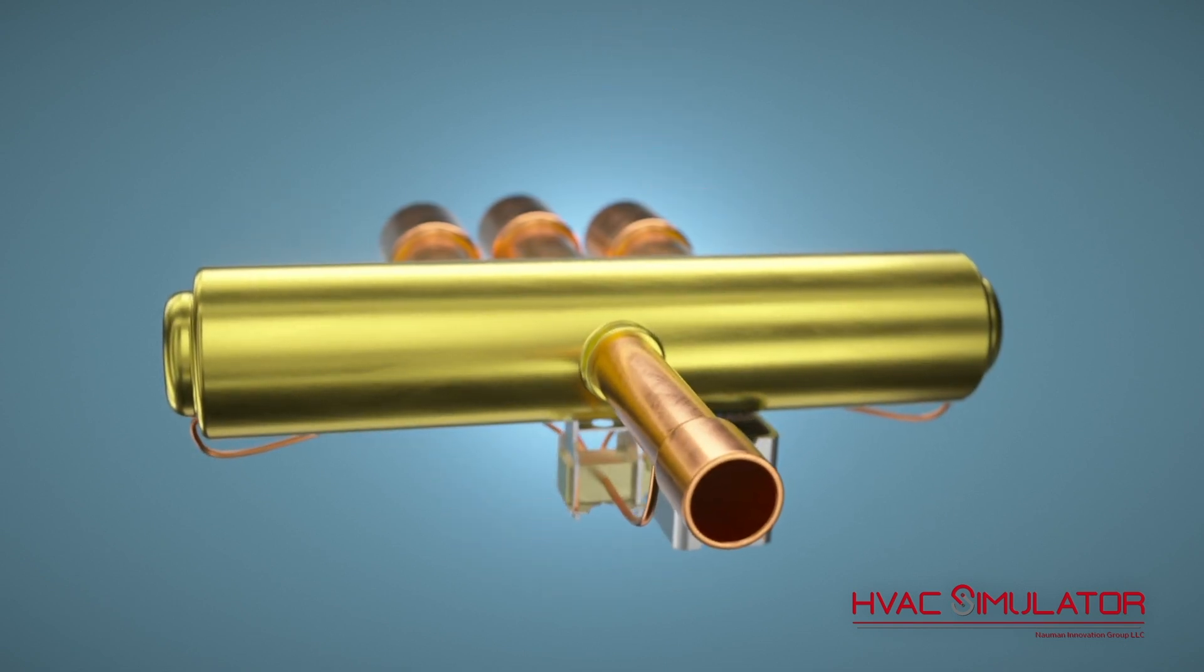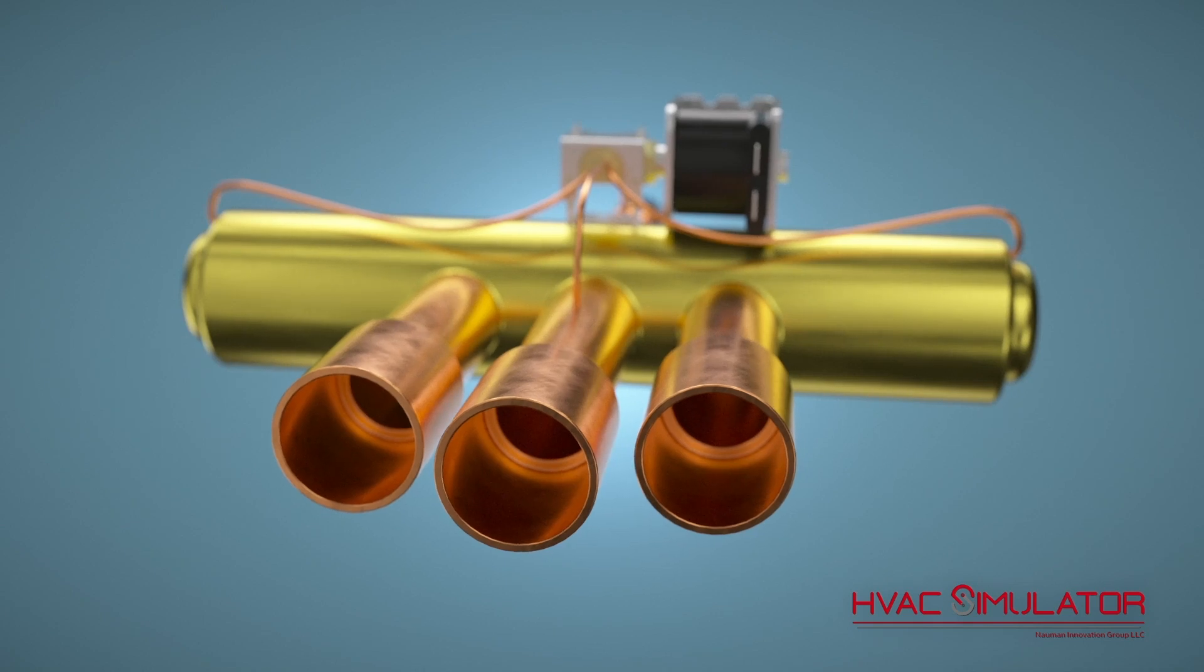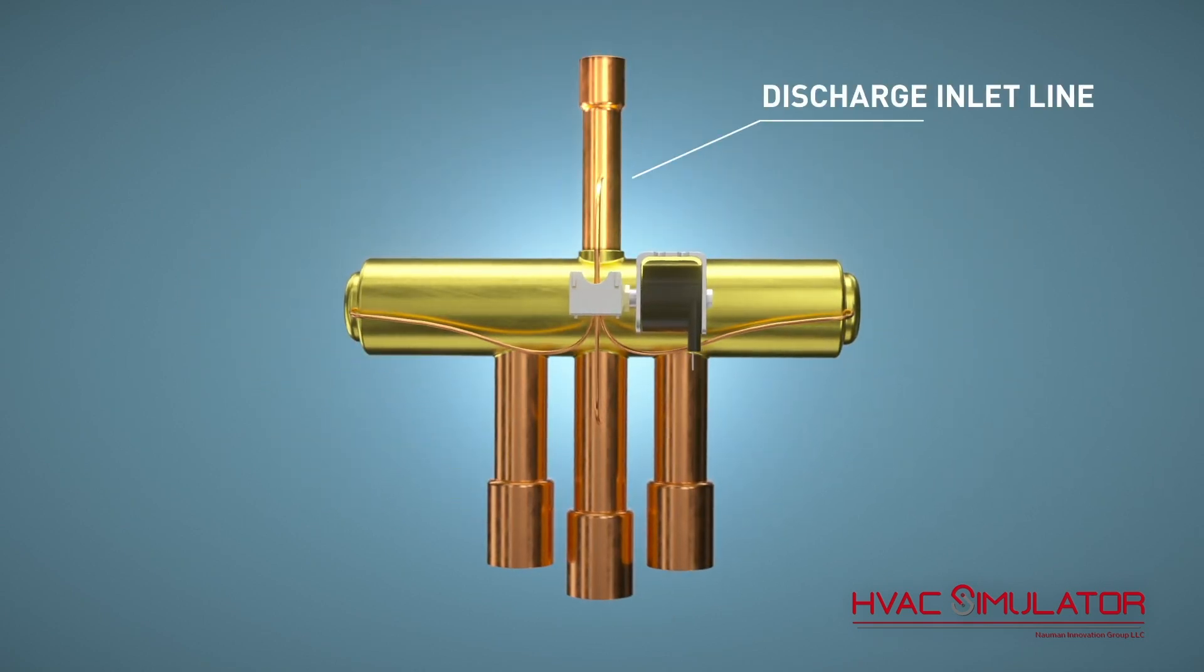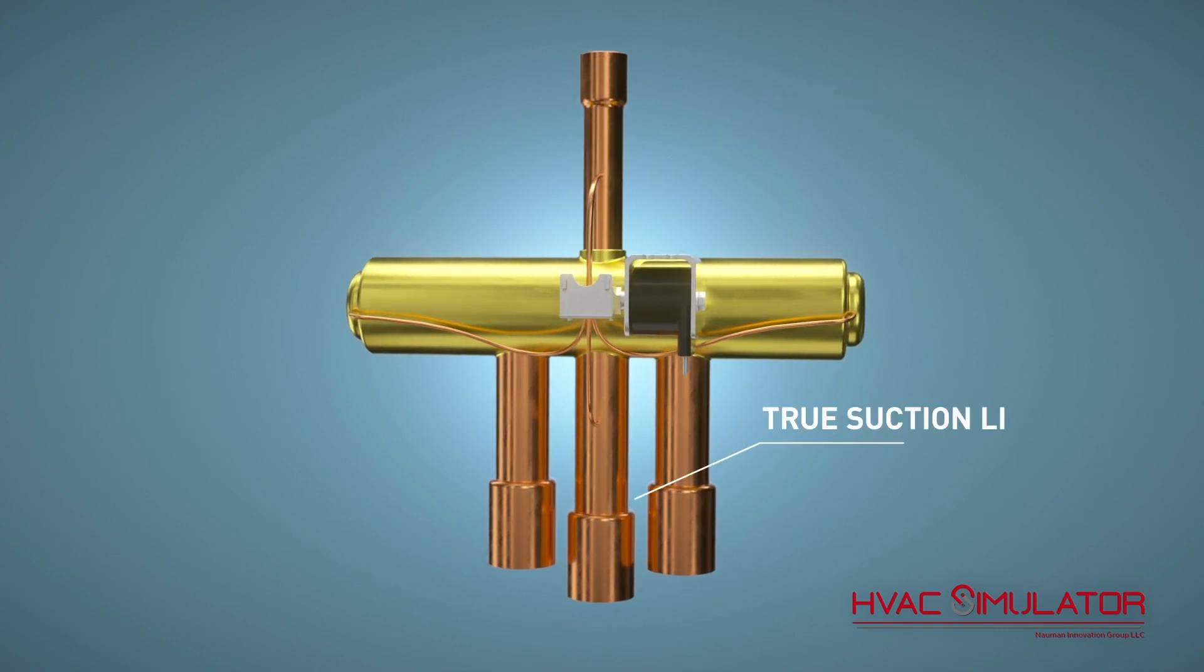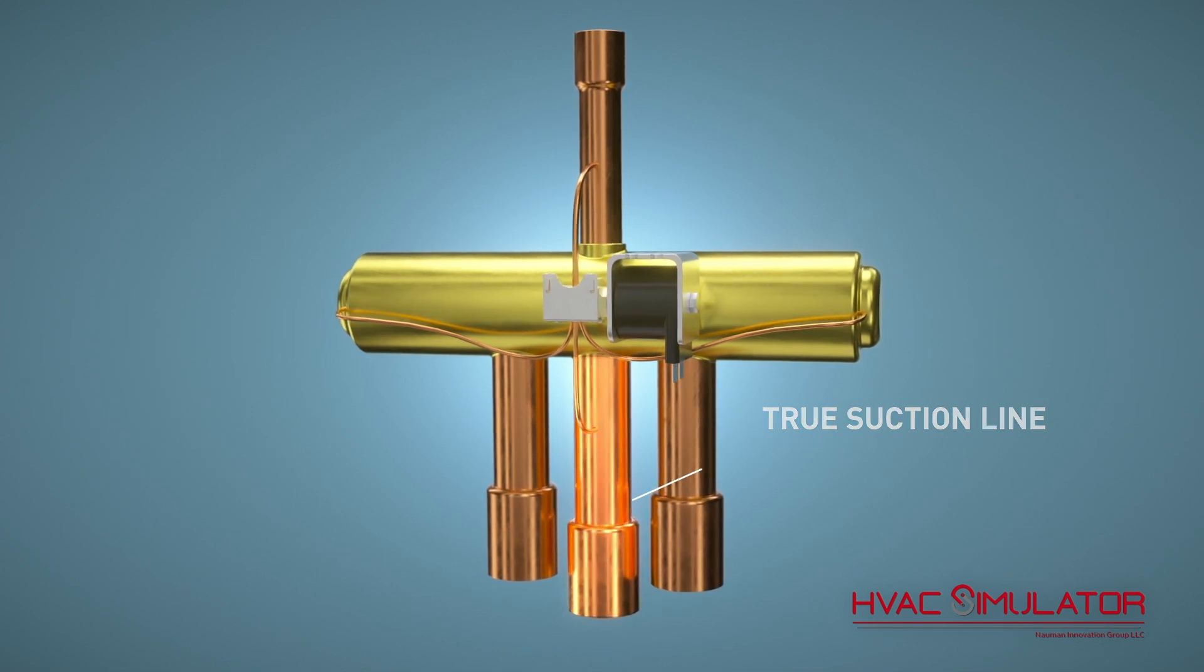Reversing valves are often called four-way valves because they have four ports or connections for refrigerant flow. The discharge inlet line will always be the single line opposite the three other lines. The true suction line will always be a low pressure outlet in the middle of the three pipes and directly connected to the accumulator.